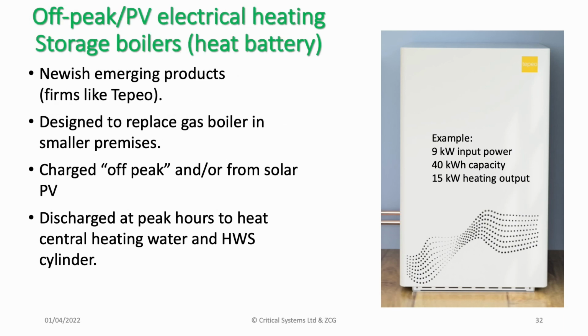It's also possible to consider off-peak storage with a so-called heat battery. And these could be fed from photovoltaic energy or off-peak power. And there are a number of products emerging, and I've just taken an example from a firm called Tepeo, and you might like to look at their information. And these are designed to replace gas boilers in smaller premises. They're charged off-peak, as I've just said, or from solar photovoltaic, and they're discharged at peak hours to provide a central heating energy source and heat for domestic hot water.